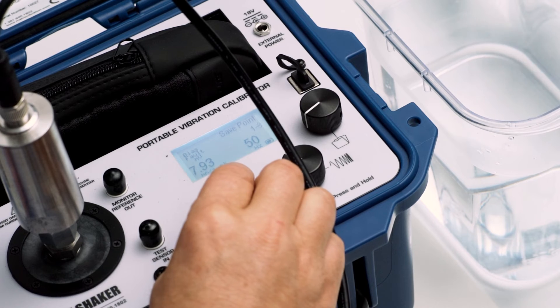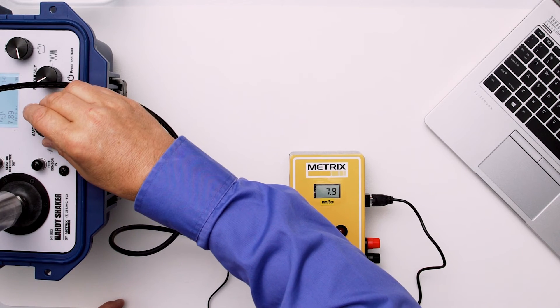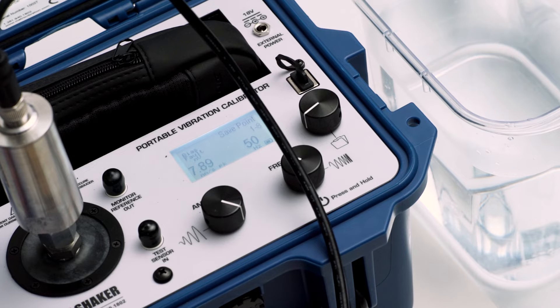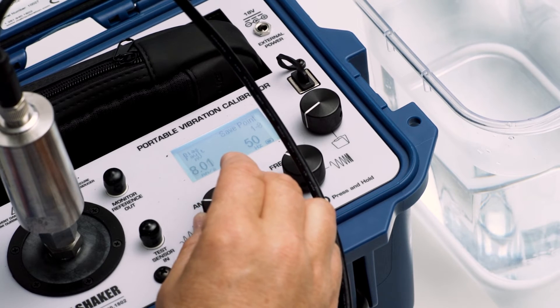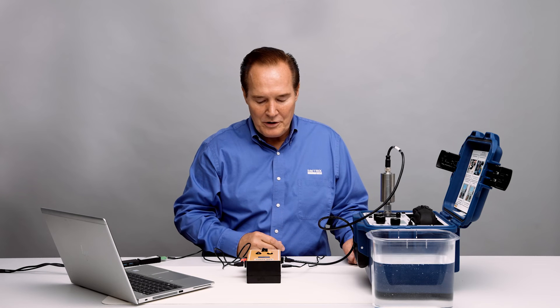Let's go to 7.9 and we'll let the alarm clear — which it does. Now I'm going to go to 8.1 and the alarm will come in. So I'm at 8.03 and it already went — so that's very good.